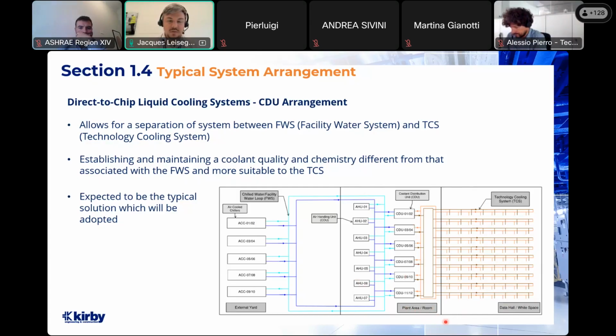So this typical solution, with some variations depending on the equipment and the arrangements, is expected to be a very typical solution on a new build direct chip system. You'll have variations of this depending on the heat rejection equipment that you're using, and depending if you're trying to install or retrofit to an existing system, but this would be a relatively typical approach.